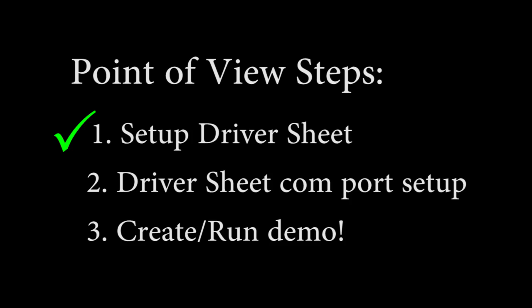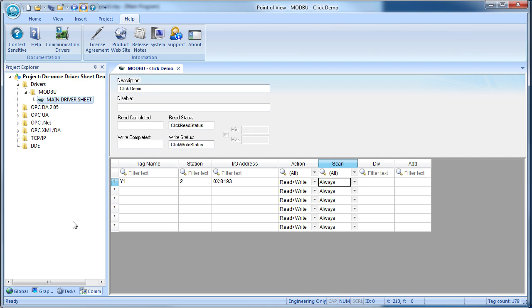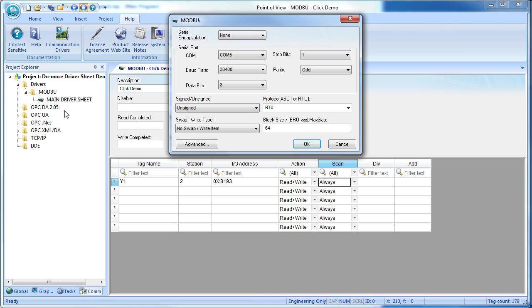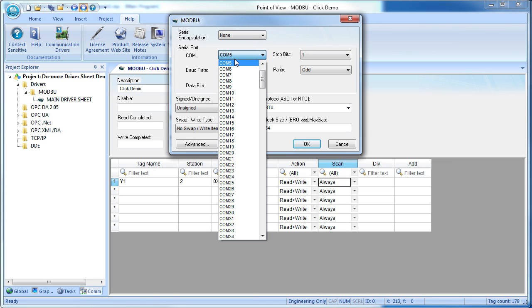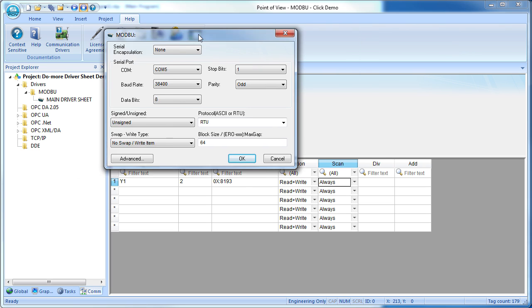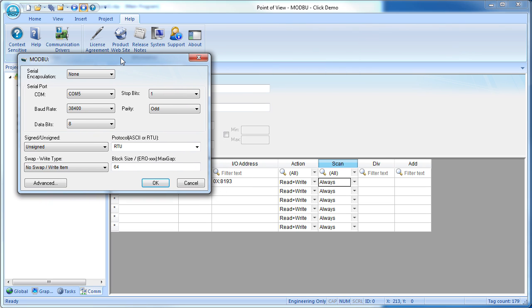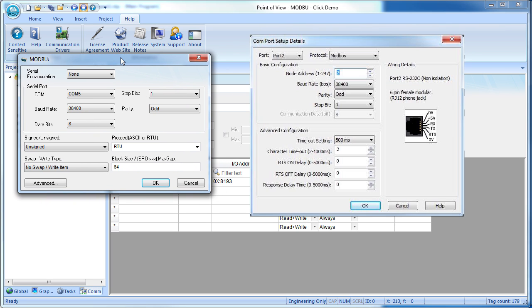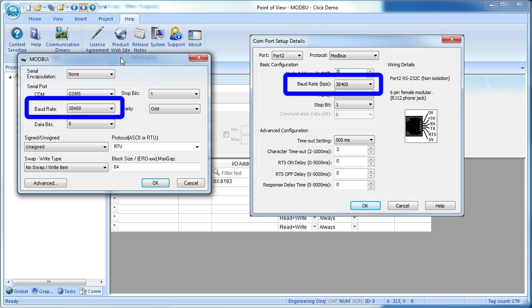To configure this serial port in Point of View so we can talk to the Click, just right-click on the Modbus driver folder and select settings. The cable we're using is plugged into COM port 5 on the PC. We want the rest of this to match the numbers we put in port 2 of the Click.